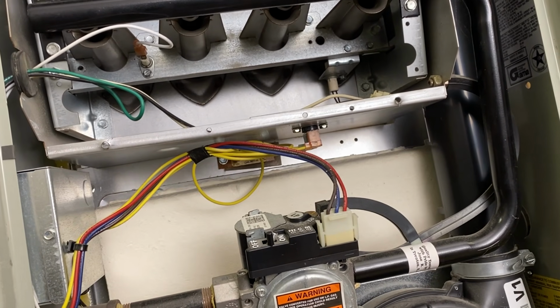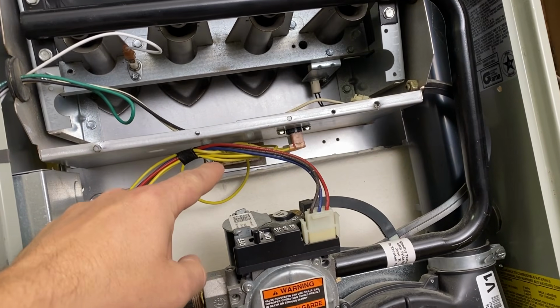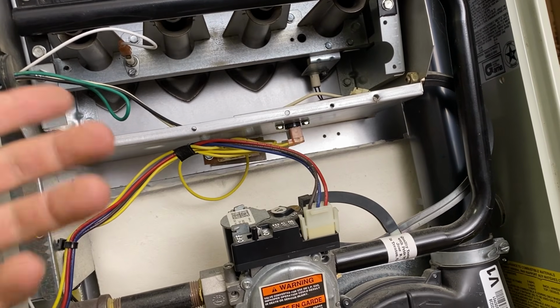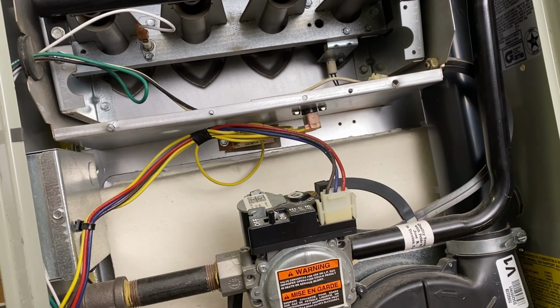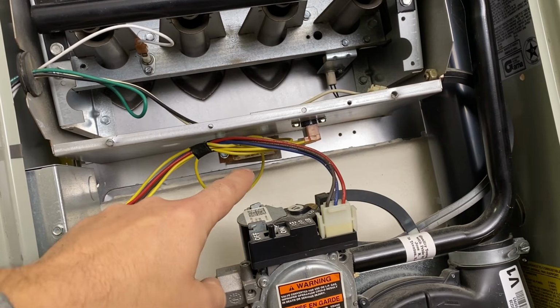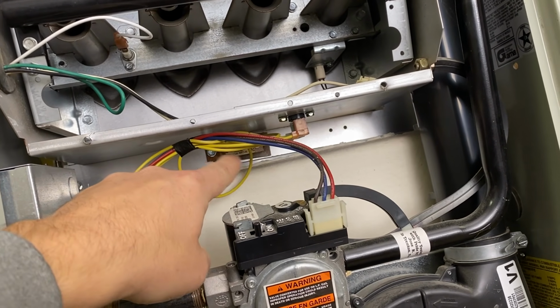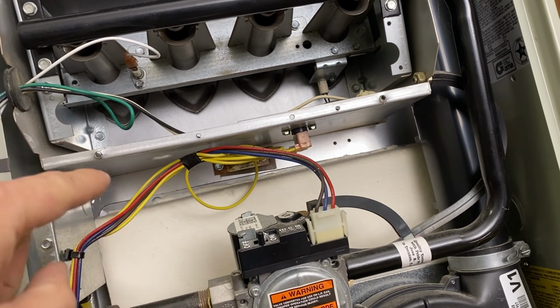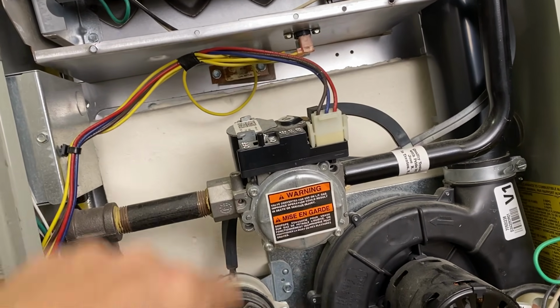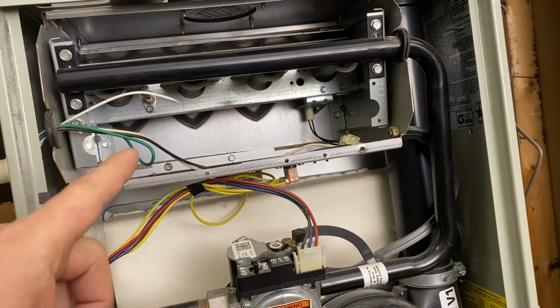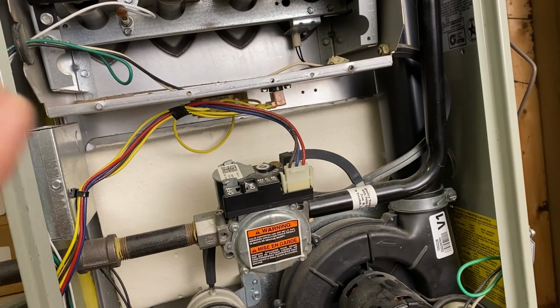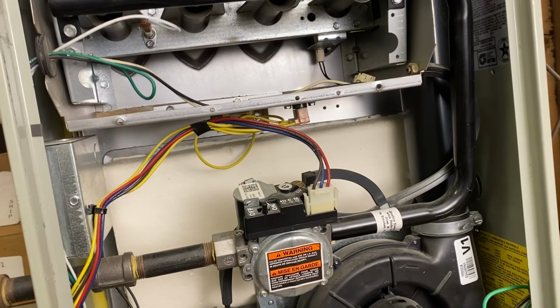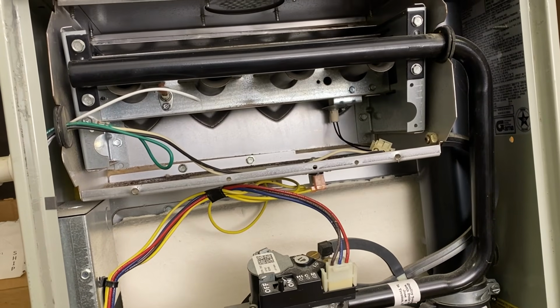So if your furnace runs for a while, then shuts off, then you might have a blower issue. Maybe something's wrong there. Sometimes the limit itself can go bad and it's not sensing any temperature, and so the blower never comes on, and then other things can happen with that. So the trouble code will tell you if that sensor is bad. Usually the limit sensor is going to be bolted right onto the back side of this little compartment here. So let's put this cover back on, and I'm going to turn ours on. I'll show you what's going on with ours, and then we're going to get it fixed and see if it runs for us.